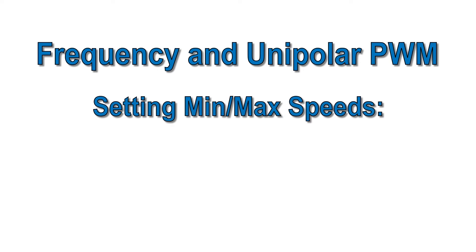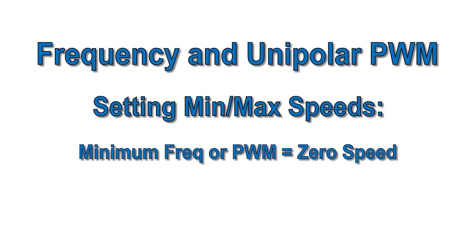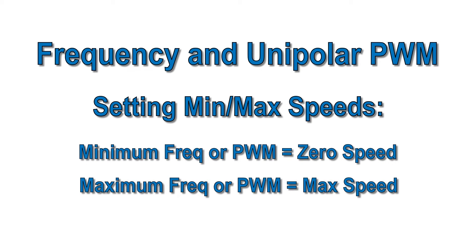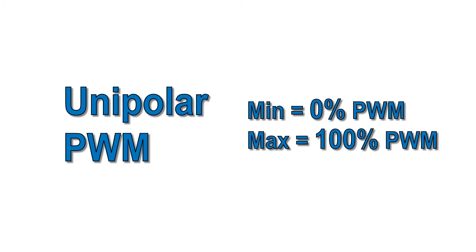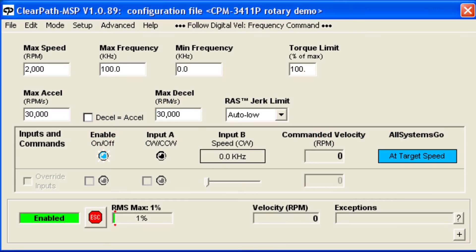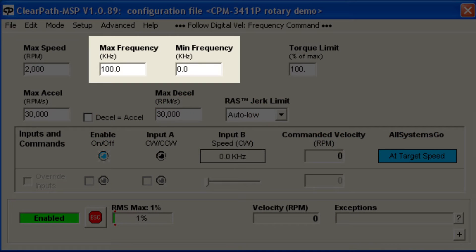Frequency mode and unipolar PWM mode work in a similar way. You have defined minimum and maximum frequencies or PWM duty cycles, and they correspond to zero speed and your user-defined max speed, respectively. For unipolar PWM, the minimum and maximum duty cycles are fixed at 0% and 100%. For frequency, the minimum and maximum are user-defined.